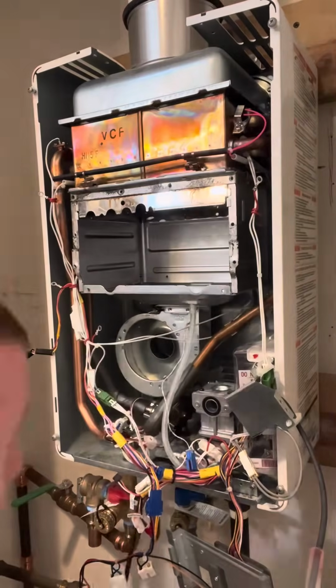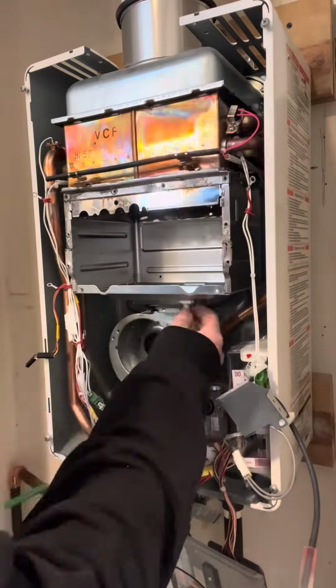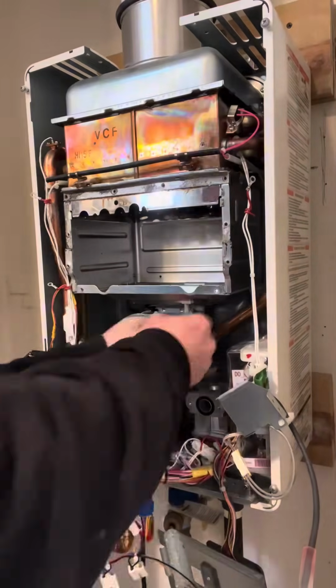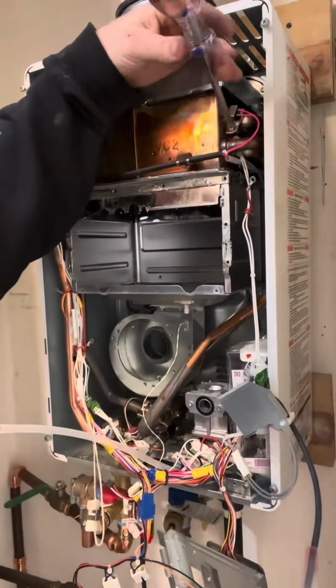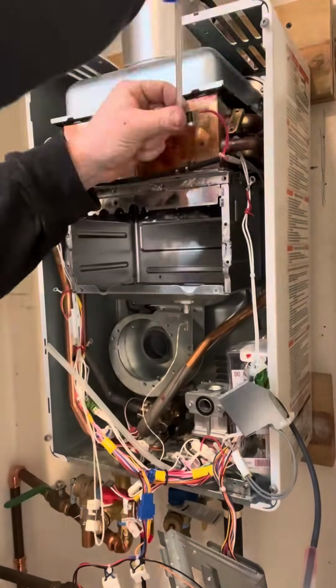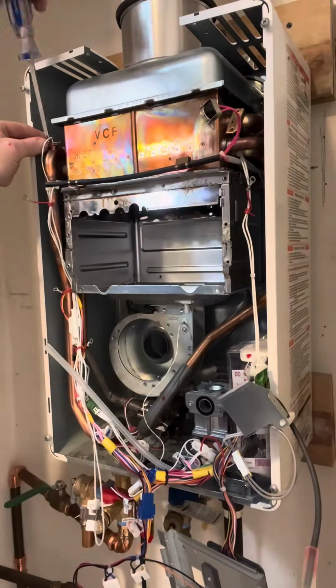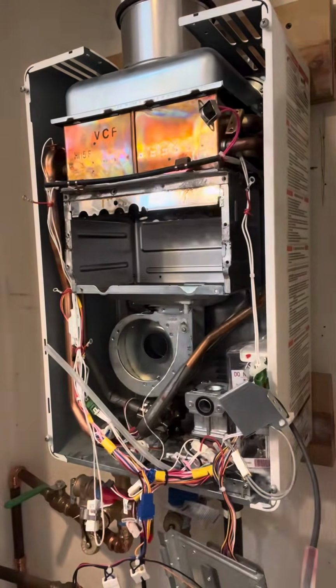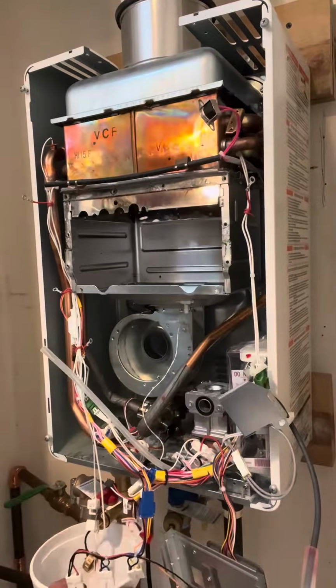Next, we're going to disconnect everything that we can see that's attached to the heat exchanger. We have this hose here, so that's just going to get pulled off. I have to disconnect 2 sensors - there's one on the right-hand side, that one just clamps onto the pipe. The other one actually goes inside of the pipe, so you're going to want to make sure that you drain the water down before actually pulling that out.